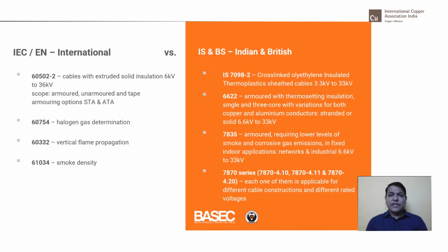So this is a comparison between the standards for medium voltage cable. IEC 60502 Part 2 is quite a popular standard used worldwide as a generic standard. In any part of the world, this is quite acceptable. In India, as you know, IS 7098 Part 2 is for medium voltage cable. You understand what medium voltage cable means: in India it is 3.3 kV to 33 kV.